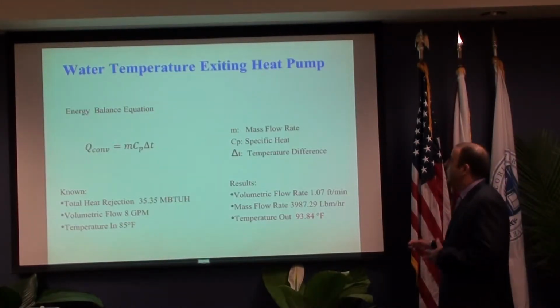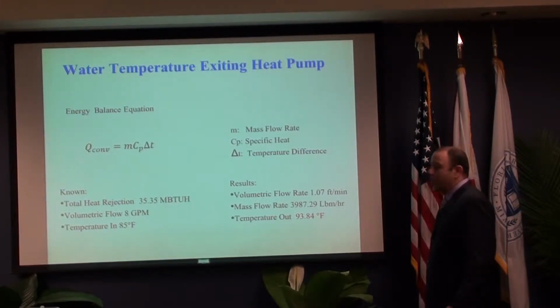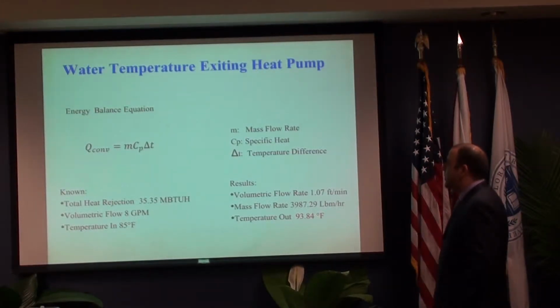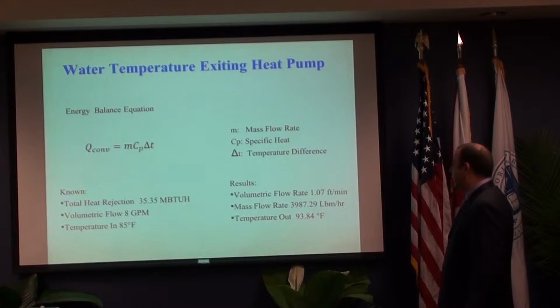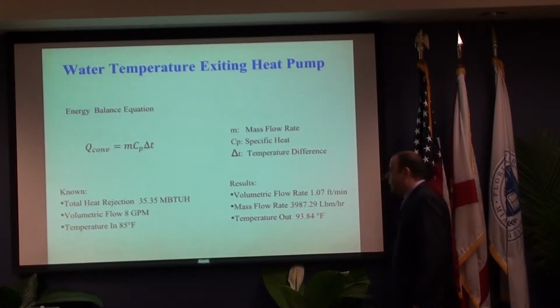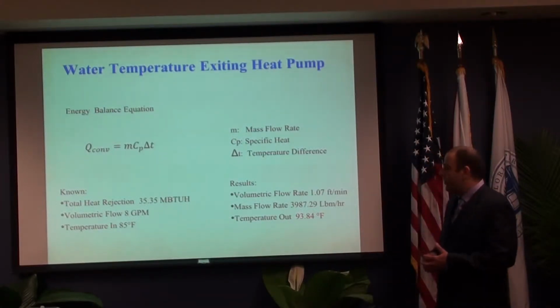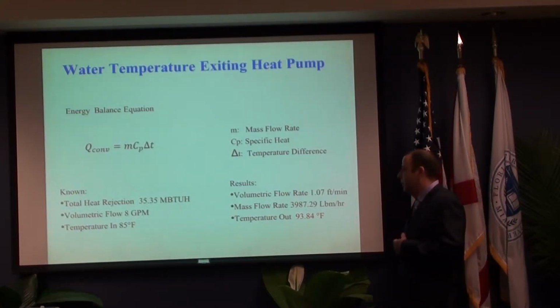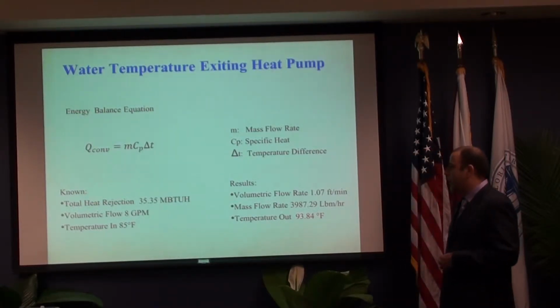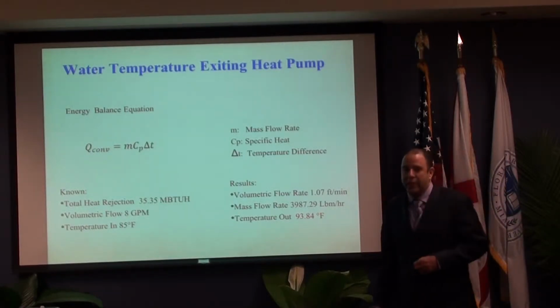We started with the water temperature in the heat pump. The equation we used was Q = m c_p ΔT, and the final temperature is 93.84 degrees Fahrenheit. From the specification of the heat pump, we know that we have 35.35 MBTU per hour and a volumetric flow of 8 gallons per minute at a temperature reading of 85 degrees Fahrenheit.